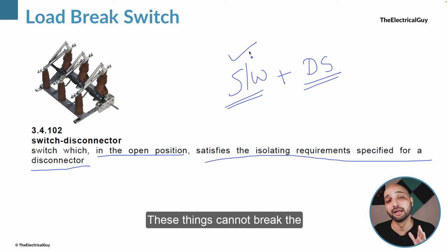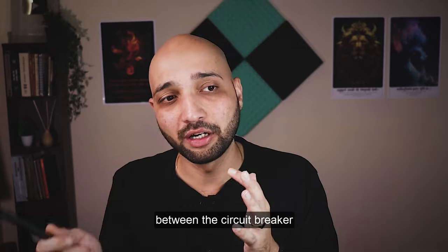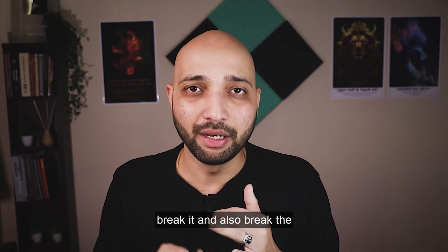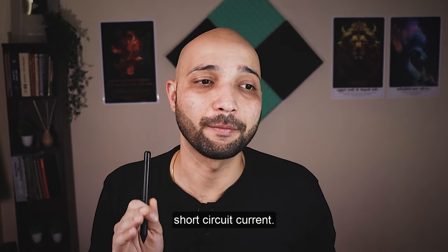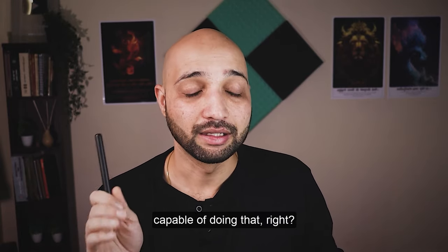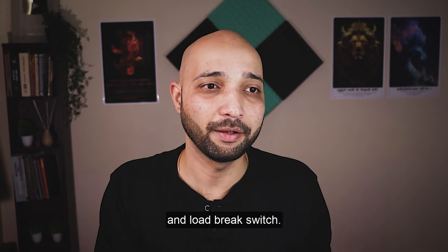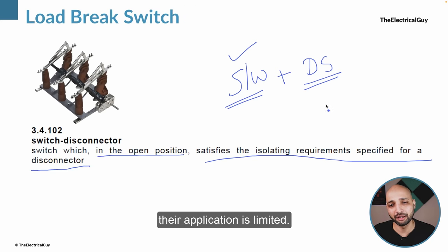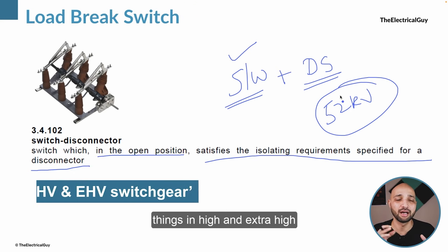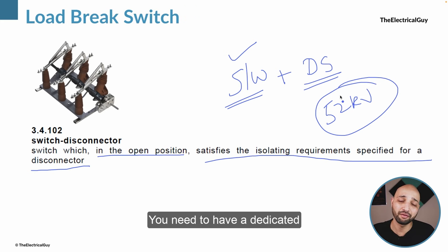Load break switches cannot break the short circuit current — keep that in mind. That is the key difference between the circuit breaker and the load break switch. A circuit breaker is able to make and break normal system current and also break short circuit current. A load break switch or switch disconnector is not capable of doing that. Also, the application of load break switches is limited to 52 kV, which is the distribution level only. At high and extra high voltage you need a dedicated isolator and a dedicated circuit breaker.